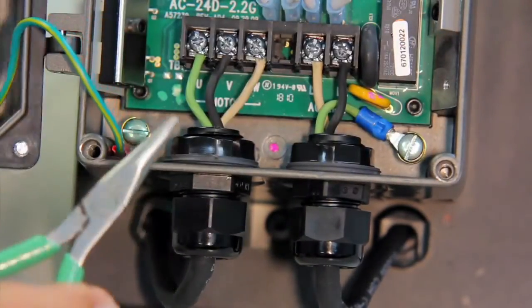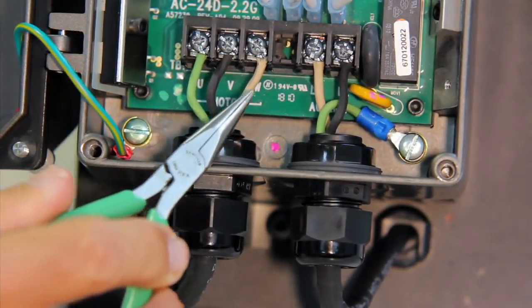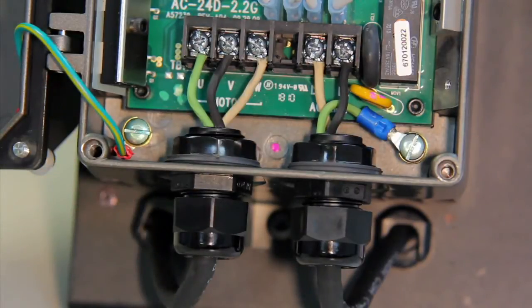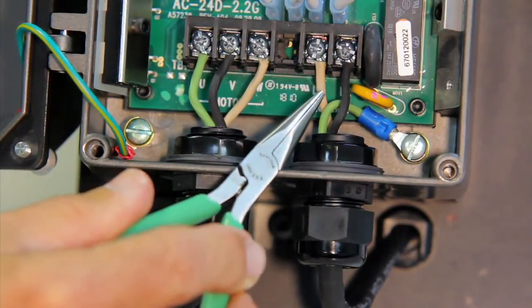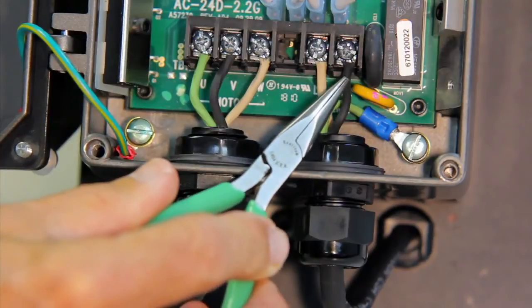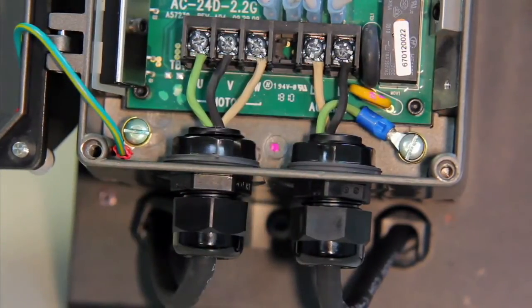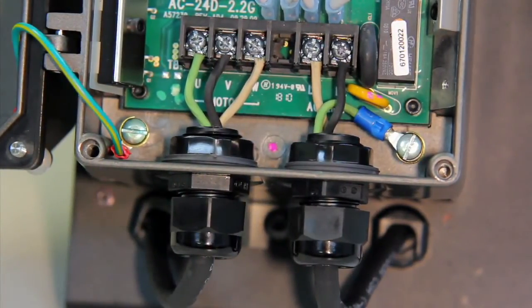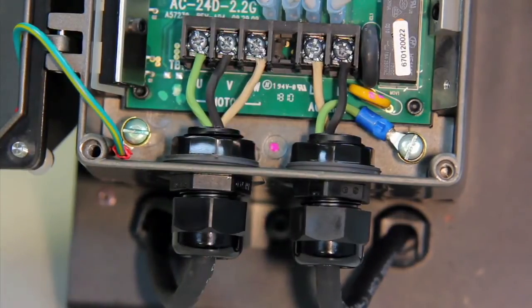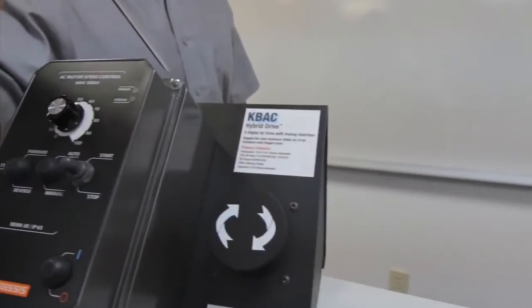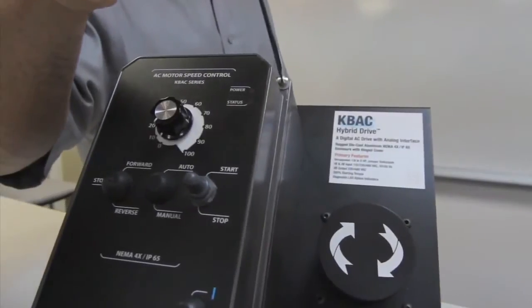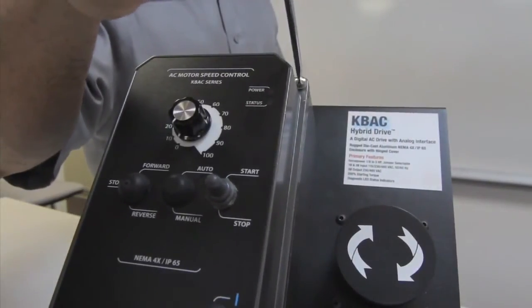The motor leads are connected to the U, V, and W terminals. The single-phase AC line input leads are connected to L1 and L2. If you are working with a three-phase drive, please refer to your installation manual for correct wiring. Once the drive is mounted and wired, you will need to determine three jumper settings.